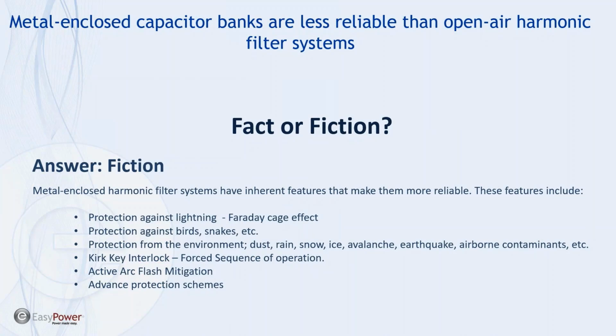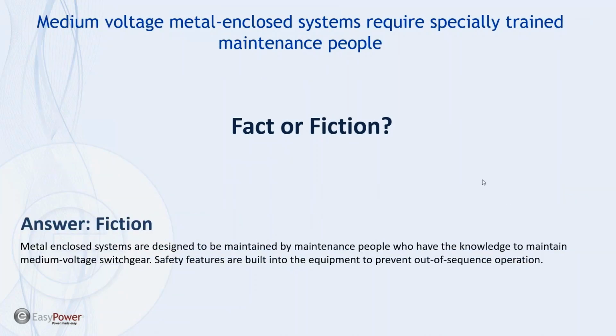And then finally, we can provide advanced protection schemes. It's very typical metal-enclosed systems are equipped with multifunction relays, digital relays, and advanced protection systems that allow for individual as well as THD harmonic detection for overload. We provide over temperature inside the enclosure, and therefore it can protect against over temperature also. So many different control and protection features that are available to help keep the system reliable.